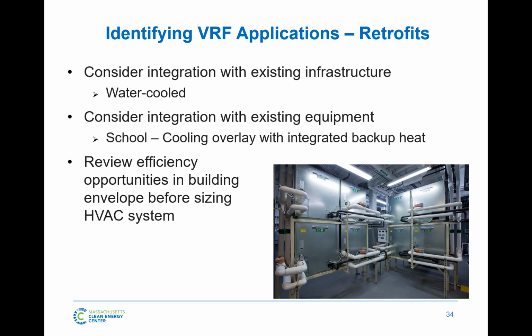Consider integration with existing equipment. VRF heat pump systems are used quite a bit for cooling overlays. So even though they are capable of being your only source of heat, I've done plenty of schools where the school was built with heating only, and now they're looking to use the school building 365 days a year, summer programs, community events, whatever it may be.